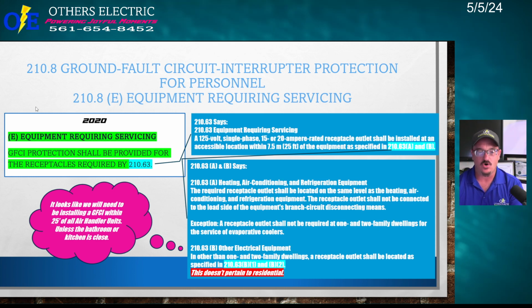So this whole section E is new. Okay? So 210.8E. This is for the residential guys. GFCI protection shall be provided for the receptacles required by 210.63. So 210.63 says, hey, you need these receptacles in your installation. Doesn't matter the installation. Residential, commercial, industrial, doesn't matter.